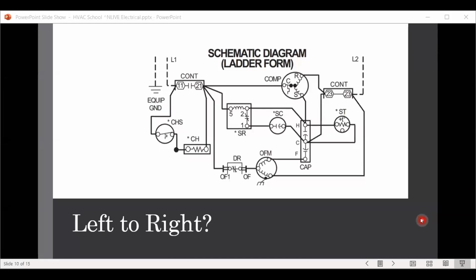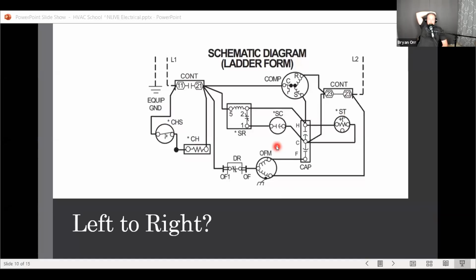So you touched on something and it kind of got me thinking. On this diagram, you've got a single pole contactor. I've seen technicians find a bad contactor and replace it and say, well, I don't have a single pole contactor, I've got a two pole contactor, and that's always better than a single pole contactor, I'll throw it on there. Well, in this case, if they do that, their crankcase heater will never energize. Am I correct? Correct. Yes. If you do it that way, your crankcase heater will never energize.